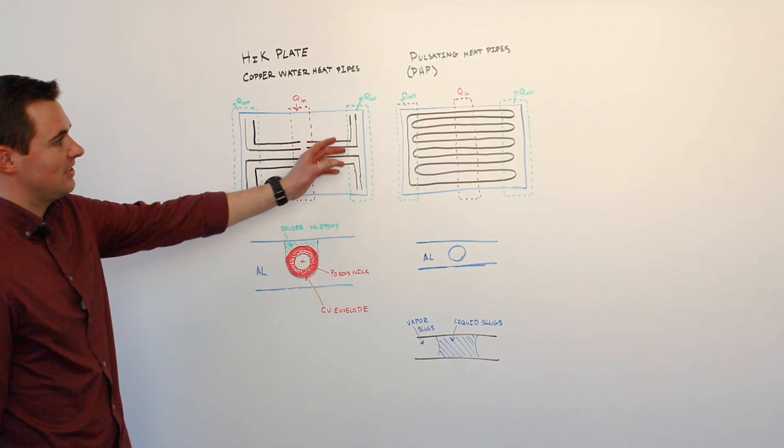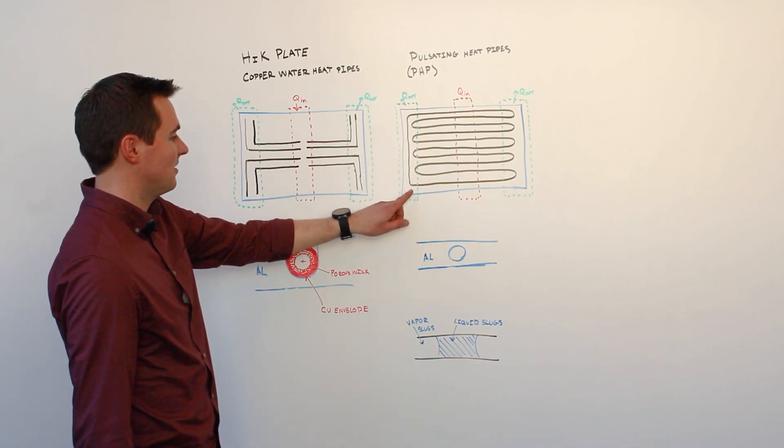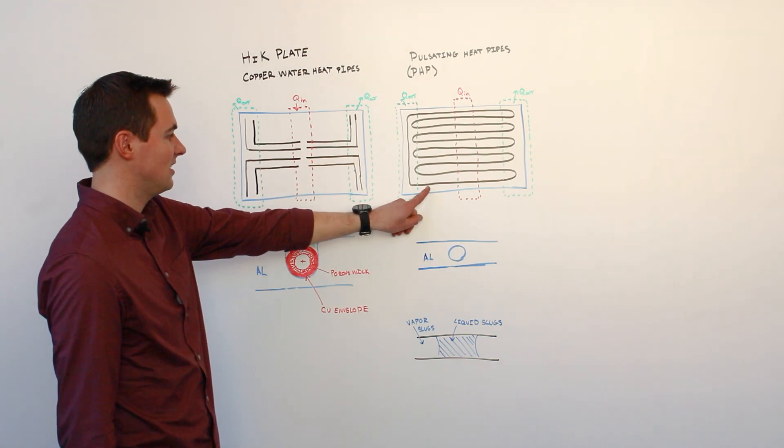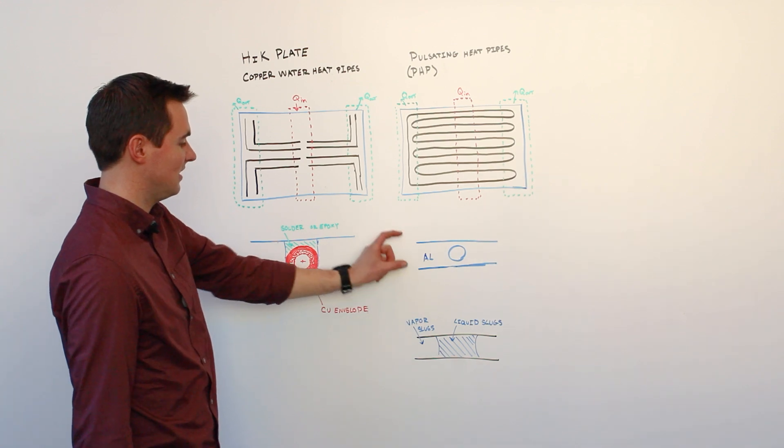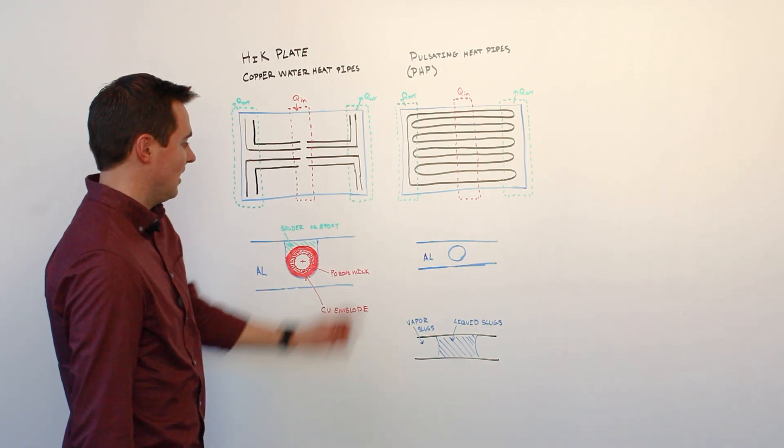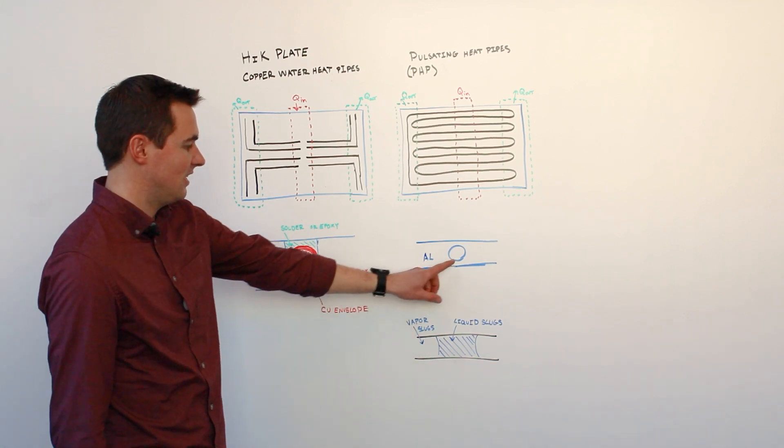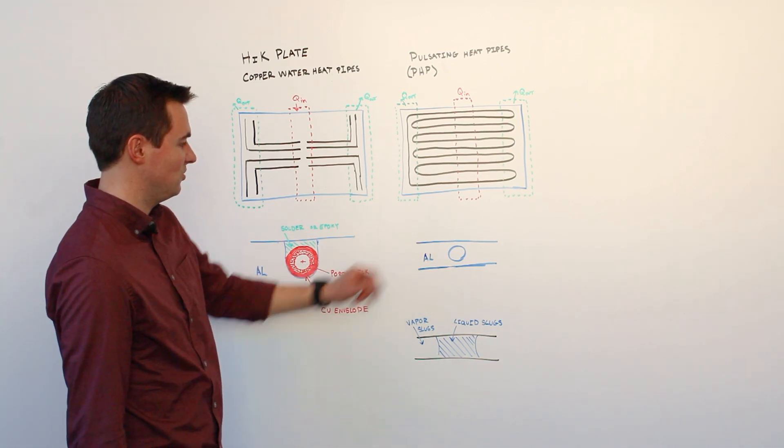Another technology is pulsating heat pipes. Again this shows a similar form factor, but in this case rather than discrete heat pipes we have a single continuous serpentine channel which is embedded within the aluminum plate. You can see that this diagram has many fewer components. It's simply a hollow serpentine channel which is manufactured within an aluminum plate.